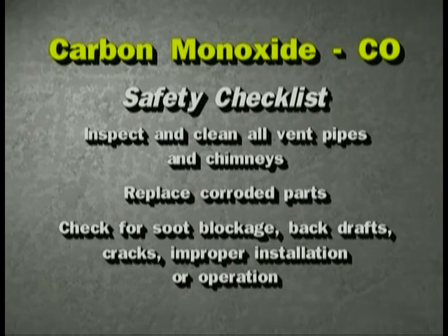If you've answered yes to any of the above statements, you need to start looking for a potential source of carbon monoxide gas in your home. Let's take a look at our safety checklist for some guidance. Inspect and clean all vent pipes and chimneys. Replace corroded parts. Check for soot or creosote blockage, bird nests, backdrafts, cracks, or staining.